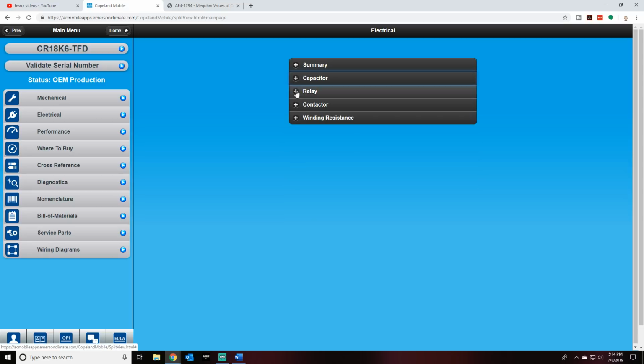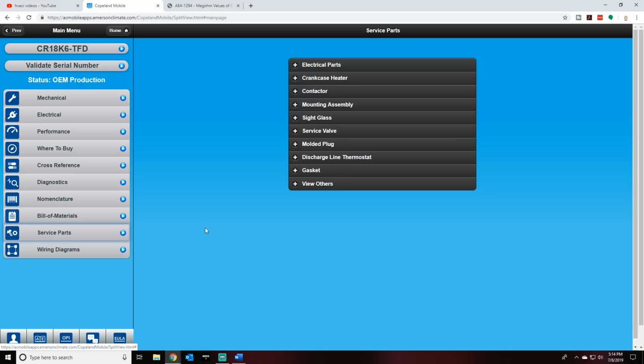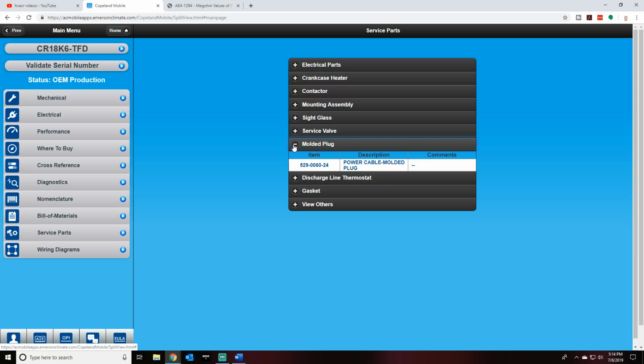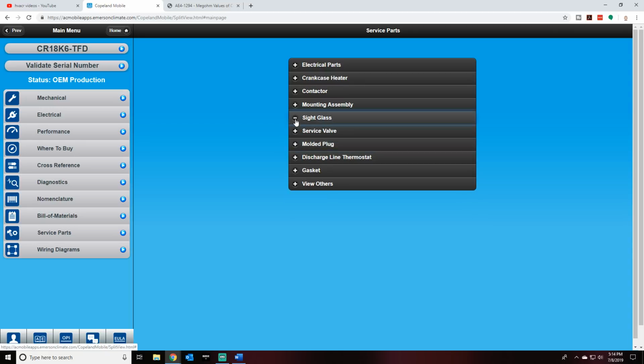You could do the same thing with a relay, potential or thermal, whatever. But this is a 3-phase compressor, so you can also look up service parts. And I really like this part because let's say this unit has a discharge line thermostat. You can click right here and it'll pop up. If it has some special gasket, if it's a semi-hermetic, it'll pop up. If it has a molded plug, this one has a power cable molded plug. There's the part number. Sight glasses.